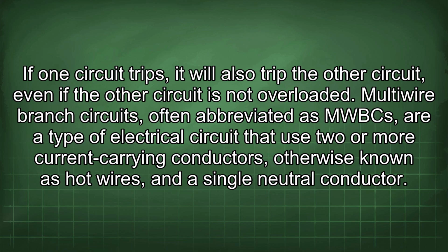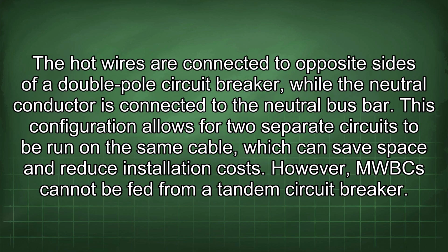Multiwire branch circuits, often abbreviated as MWBCs, are a type of electrical circuit that use two or more current-carrying conductors, otherwise known as hot wires, and a single neutral conductor. The hot wires are connected to opposite sides of a double-pole circuit breaker, while the neutral conductor is connected to the neutral bus bar. This configuration allows for two separate circuits to be run on the same cable, which can save space and reduce installation costs.